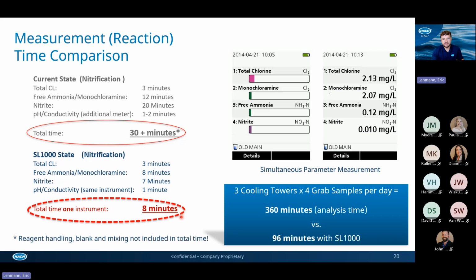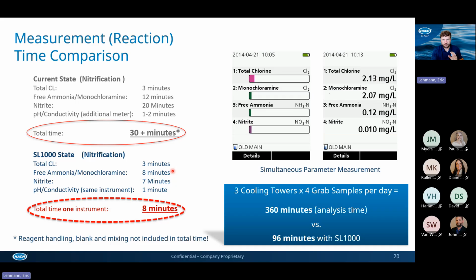When we're talking about the SL1000, we're looking at 8 minutes total. The limiting factor is the 8 minutes for the color development, or the reaction time, for the free ammonia and monochloramine. You can see the other ones run 3 minutes, 7, and 1 minute. It measures these different parameters all simultaneously. So when the 1 minute or the 3 minutes comes up for the total chlorine, it gives us our concentration. Once the free ammonia and monochloramine comes up, it gives us concentration. And after 7 minutes with the nitrite, it gives us our reading.